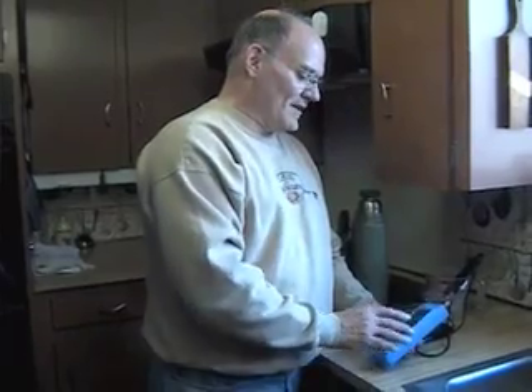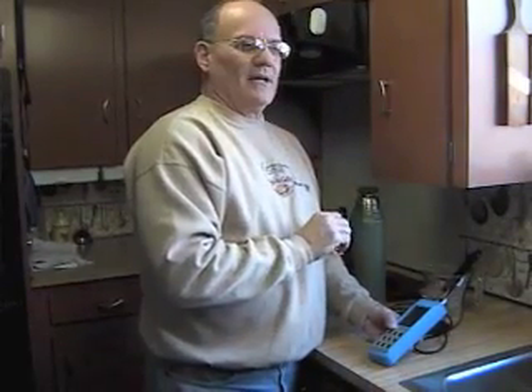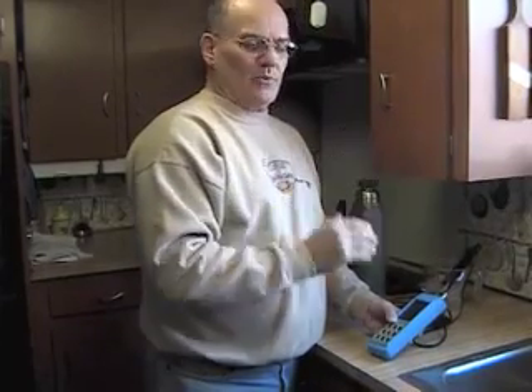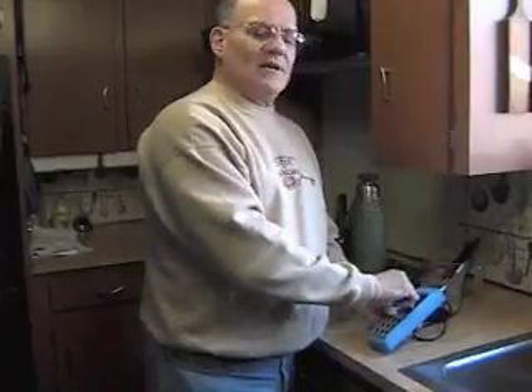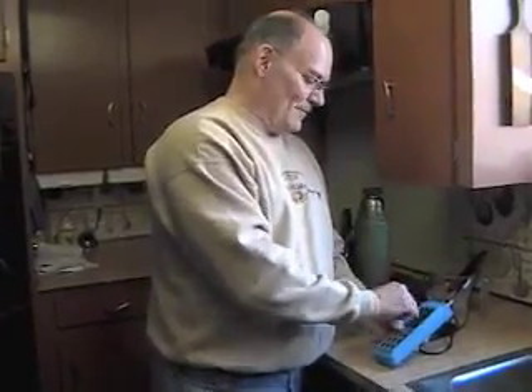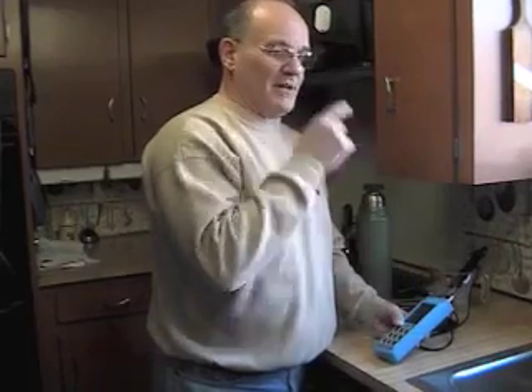Alright, so you saw the temperature changing there. When the temperature settled down around 50 degrees, 52.3, I incremented the up arrow button to go up to that temperature. When my temperature on the bottom, where the temperature is supposed to be, matched the large display temperature, I hit the confirm button, and I did my 2-point temperature calibration. That was complete. Alright, then you could turn the meter off, and just turn it back on and let it condition and go through the calibration procedure that we discussed previously.